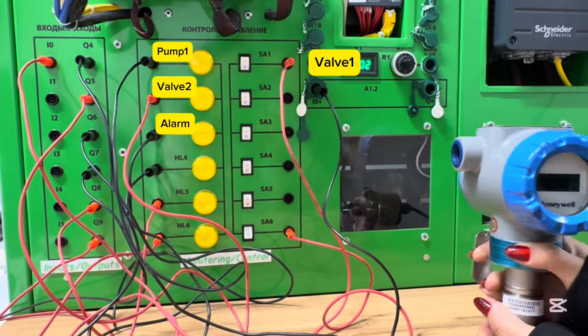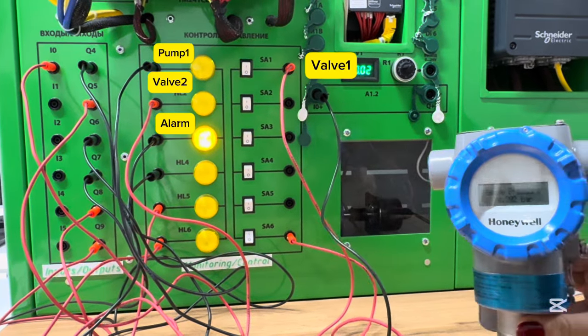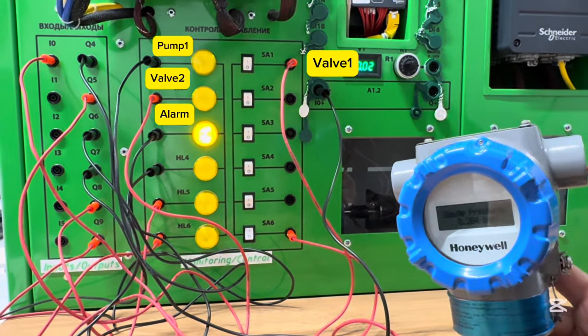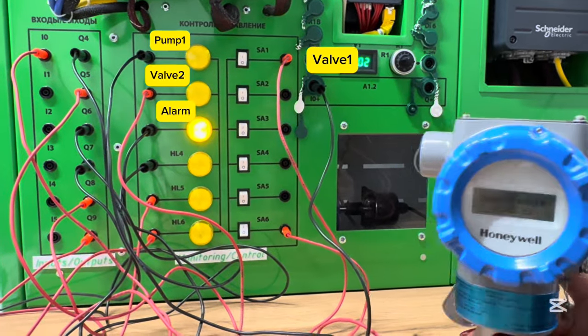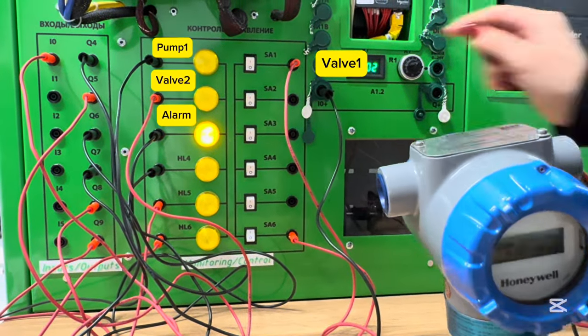Since the pressure transmitter is connected to the controller, the video begins with an alarm. The pressure is outside of the allowed range. The system requires the pressure to stay between 2 and 23 bar, and any deviation immediately triggers an alarm.